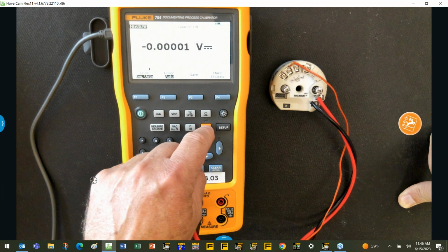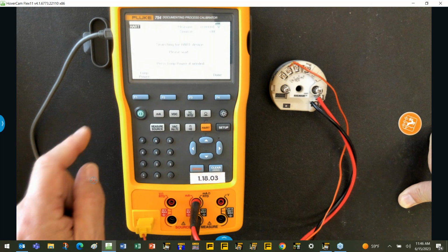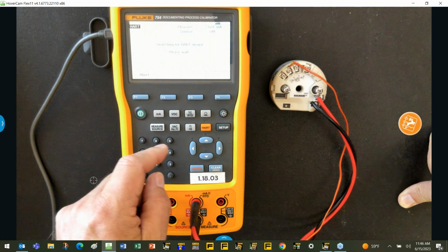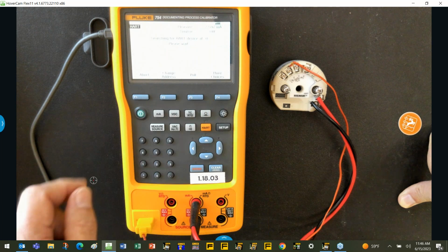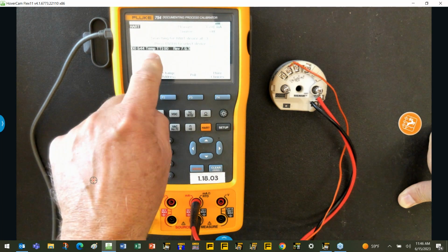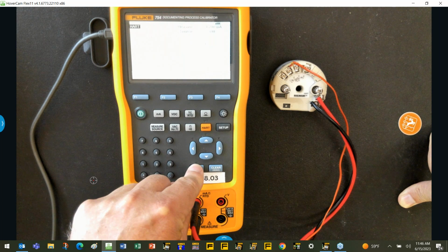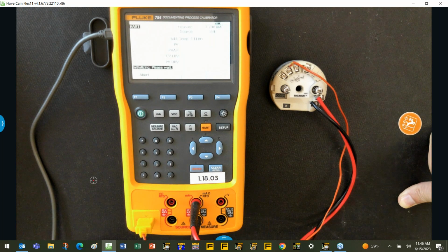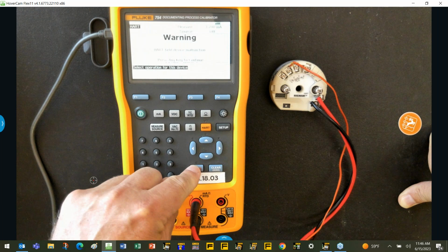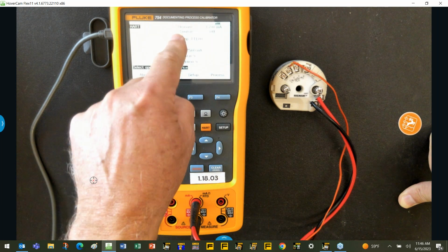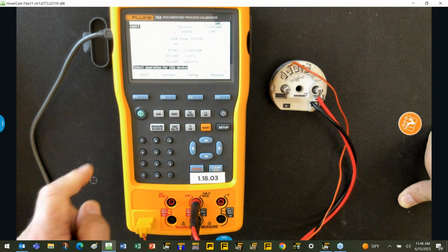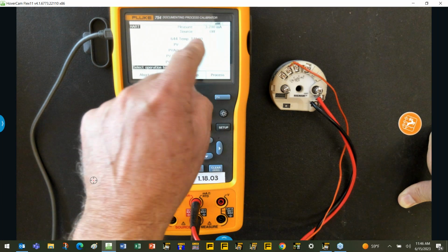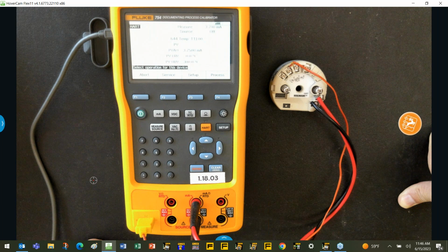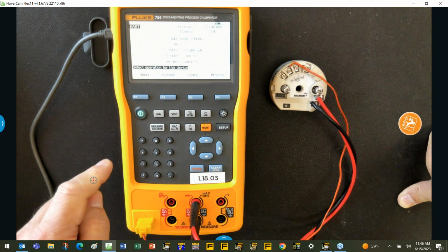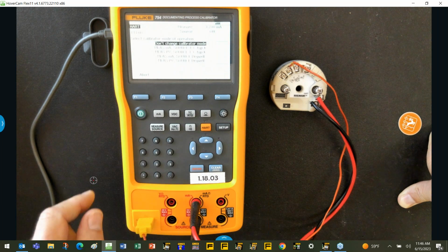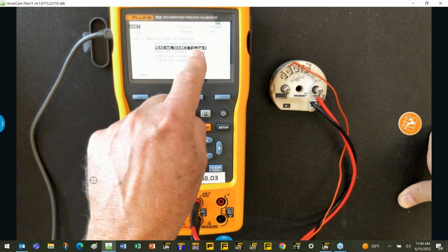So this guy's going to be sourcing the type K millivolt values to the transmitter to test it. So I'll go ahead and press HART, enable loop power, and then we're going to poll it, check for that device, and there it is right there, TT100. So go ahead and enter that. Now this screen is going to come up, and it's going to show you basically the information on there right now. Notice there's no source at this time, and that's why we got an error message. So we're going to go ahead and start the calibration. So I'll press the HART button again, hit that we're going to source type K thermocouple.